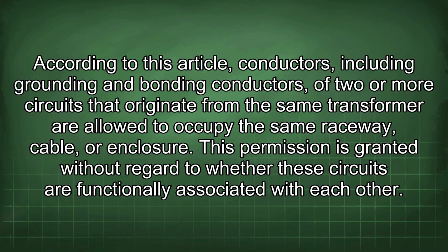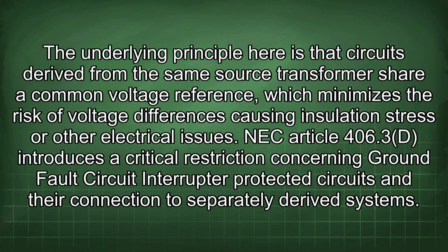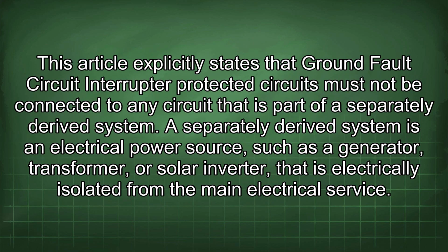This permission is granted without regard to whether these circuits are functionally associated with each other. The underlying principle here is that circuits derived from the same source transformer share a common voltage reference, which minimizes the risk of voltage differences causing insulation stress or other electrical issues. NEC Article 406.3d introduces a critical restriction concerning ground fault circuit interrupter protected circuits and their connection to separately derived systems. This article explicitly states that ground fault circuit interrupter protected circuits must not be connected to any circuit that is part of a separately derived system.